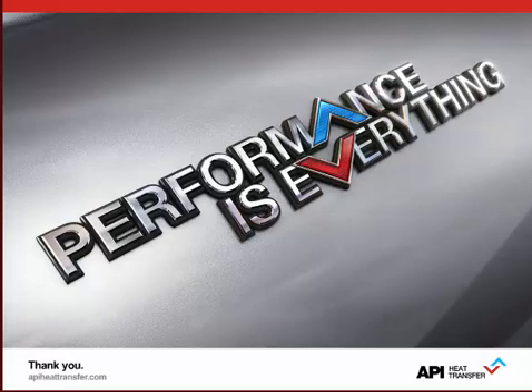So we try to point those out and work with our customers to keep the cost down. All right, thank you. Go ahead, Sebastian. Just in addition to the plate heat exchanger discussion we just had, there's also an API standard for plate heat exchangers, which is API 662. That can be applied to plate heat exchangers, and it's quite common to use this standard.